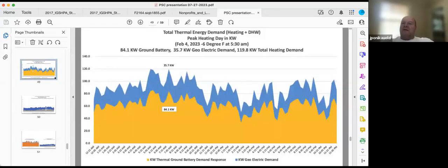So if you're looking—I can only emphasize this on the graph here—you see this is measuring the amount of kilowatts displayed or delivered, and this is the amount of total energy use of the building. This is only the thermal load. You can see this coming from the grid, about 35 kW at peak time, but 84 kW is coming from the ground battery. So up here, this is the total energy use in terms of the thermal use of the building, which at peak time is 90% of the total energy use.